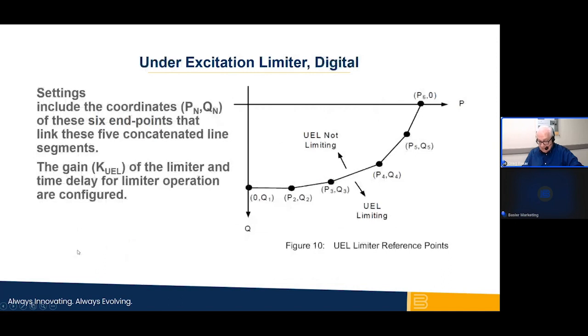The digital UEL has the flexibility to define a pickup curve that is not an arc of a circle. Users can base the path of this limit on more than one harmful condition of the machine.